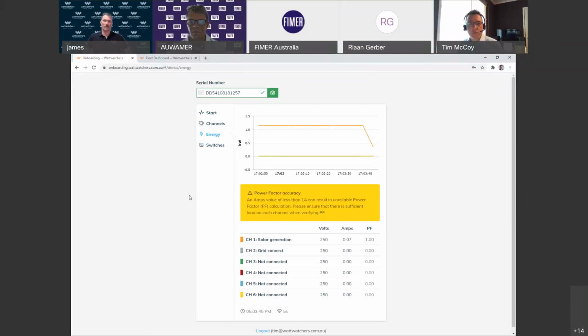There you go, hopefully you can see that as well. That's already responded to the DRM signal and has ramped effectively down to 0 generation. So that is a successful test of the disconnect function. This is essentially the way the system responds when South Australian Power Networks issue their signal as well. This is just a field test version of that.